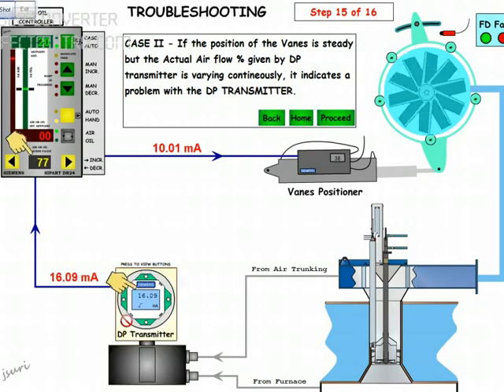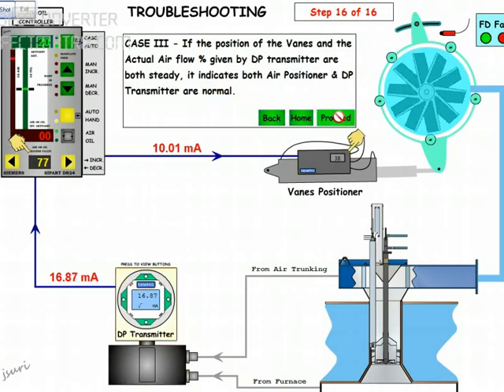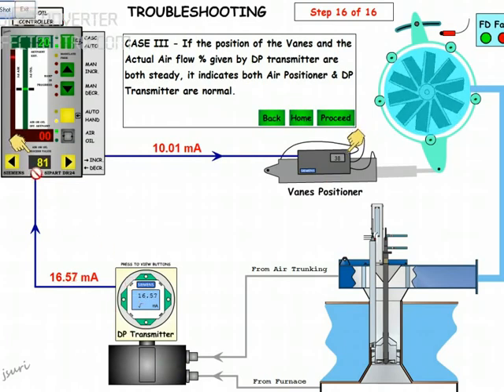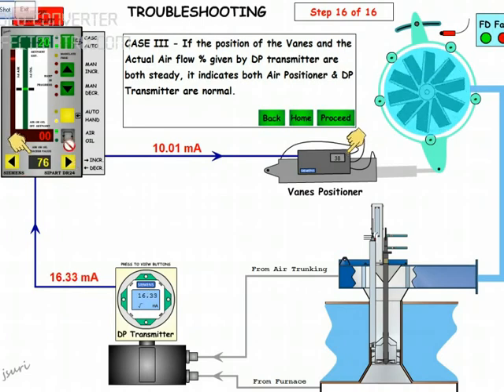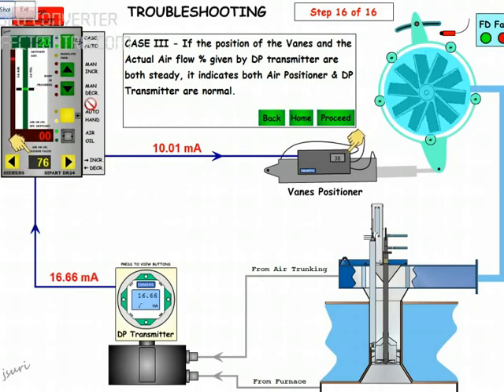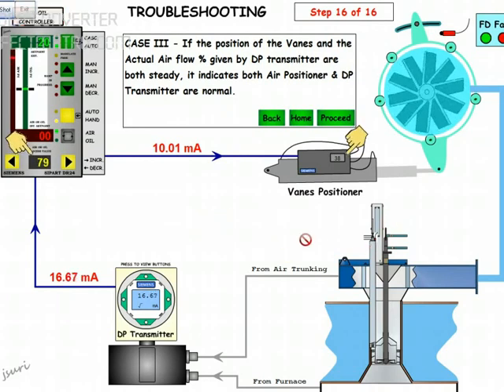Case 3: The vane position is okay, the DP transmitter is also okay, but you can see it is still fluctuating. The third problem is with the air oil controller, so you have to change this. This is how you check. If you have any doubt regarding this, you can message me. Thank you.